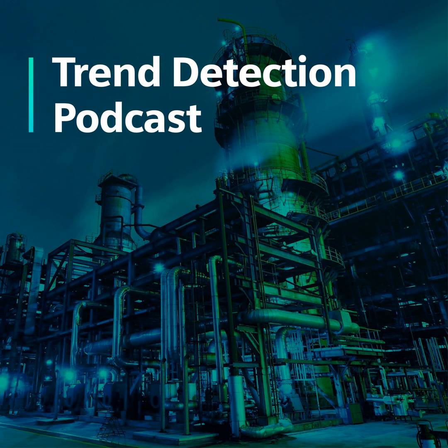We don't want to alert someone when the current increases just because you've turned up the speed of the fan, but that's very hard to model, to say the difference between when a fan is increased in speed and when it's deteriorating. Provide the right information and you can get a much more accurate idea of the condition by saying, actually, we also provide the speed. The current went up, but the speed didn't, an indication that there's degradation of the asset, or vice versa. We asked the speed to increase, but the current didn't increase. There may be a control loop problem, or actually the fan's blown off and it's actually not doing anything at all.